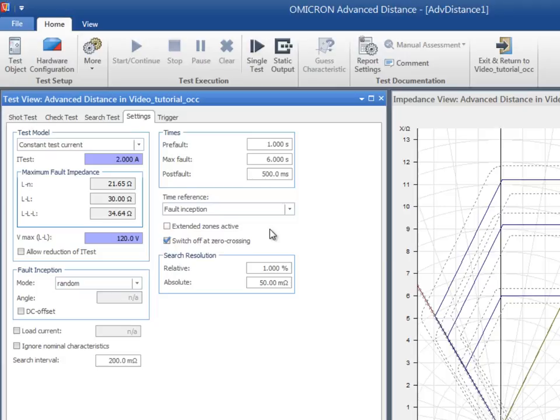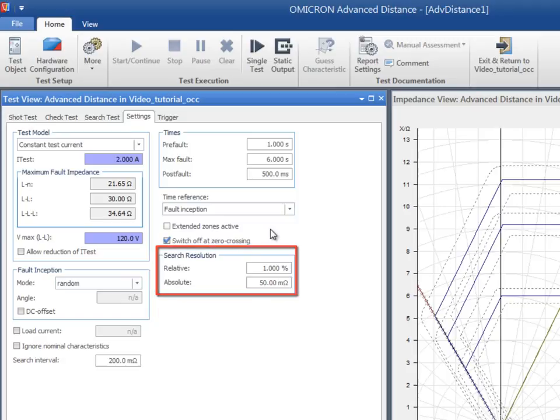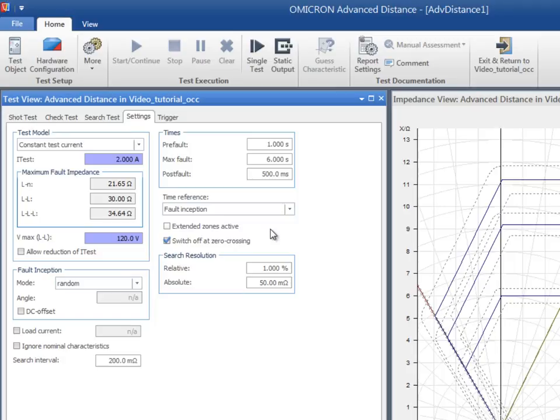The accuracy of the search test is determined through the search resolution fields. The larger resolution of either the absolute or the relative search resolution is applied. The search for the actual reach impedance stops when the difference in impedance between two consecutive shots is less than the given search resolution.